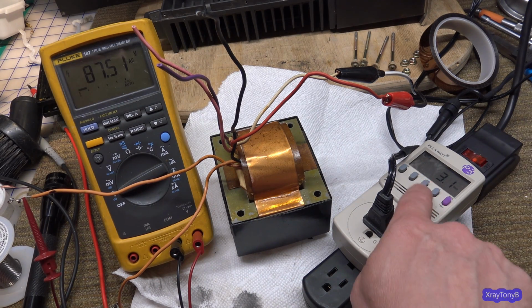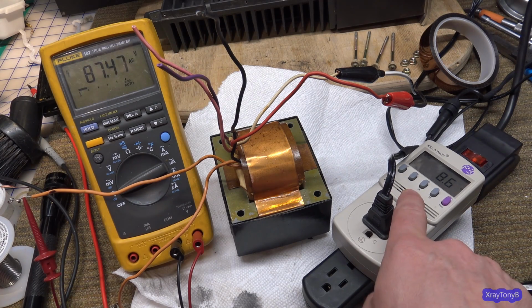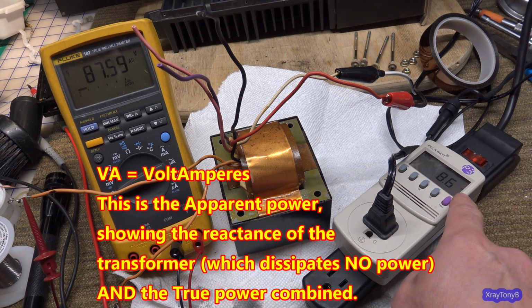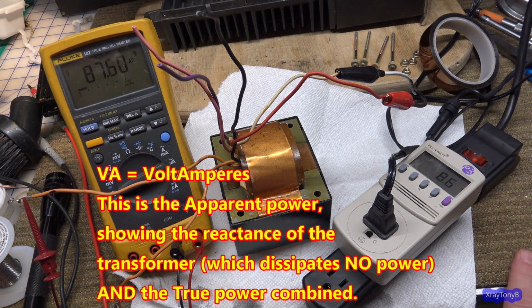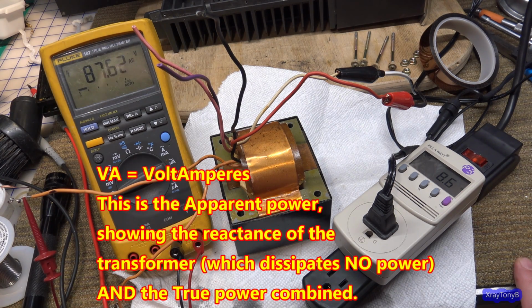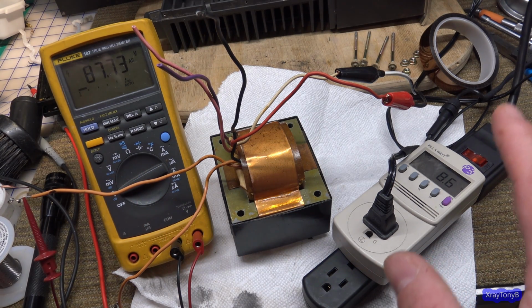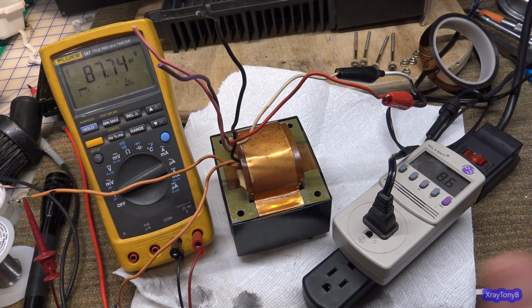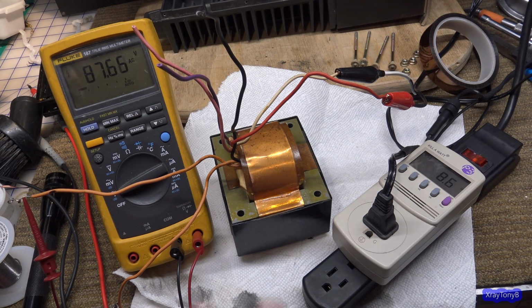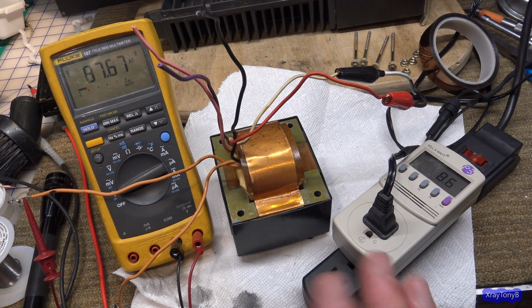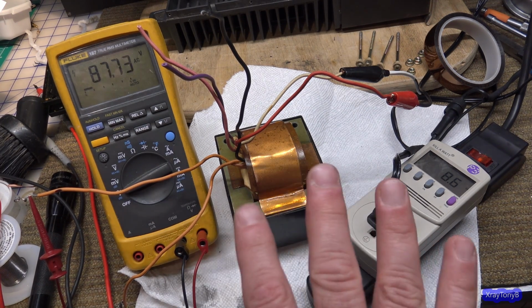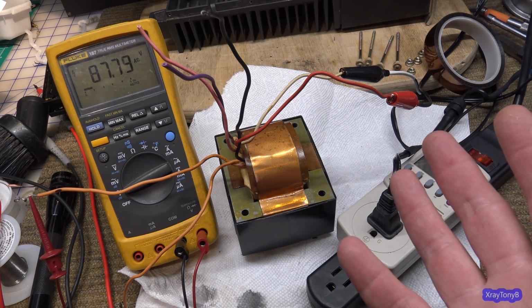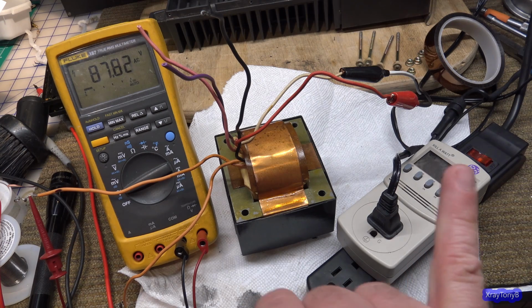But there's a little more to that. If we go to the VA rating, it's actually higher. You're dissipating about 8.6 volt-amperes, or VA, of power. And why is that? Well, what is VA in the first place? VA, or volt-amperes, is the voltage times the amps, which is similar to what watts is in DC terms. Watts is volts times amps, times the power factor.